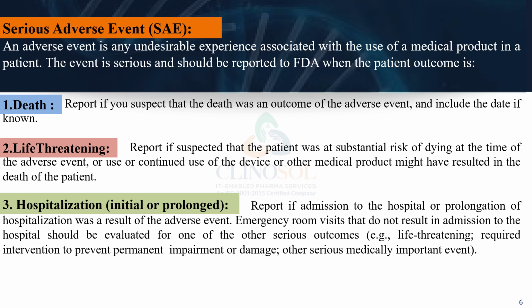Death. If you suspect that the death was an outcome of an adverse event, it should be reported to FDA, and include the date if known. Life-threatening. If the patient was suspected to be at substantial risk of dying at the time of the adverse event, or use or continued use of the device or other medical product might have resulted in the death of the patient, it should also be reported to FDA.